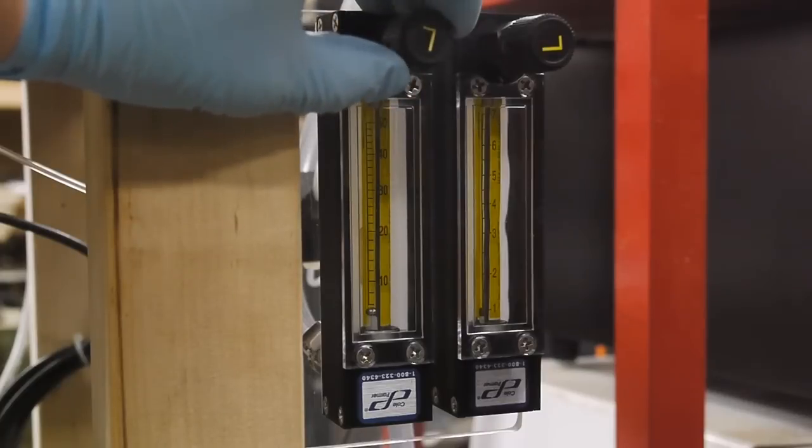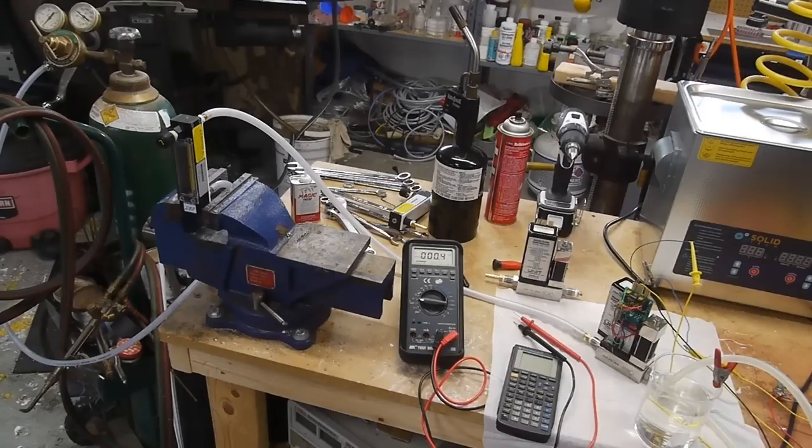So what these meters are actually measuring is the volume flow rate. They don't actually know how dense the gas is and if the pressure goes up or the temperature changes then the density will change and a different amount of gas will flow through the meter for a given flow rate.